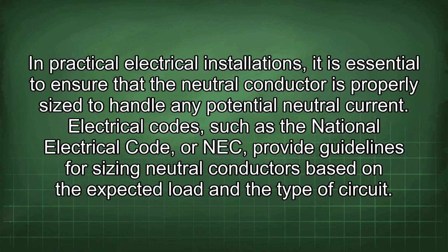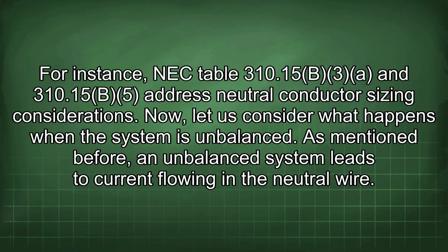In practical electrical installations, it is essential to ensure that the neutral conductor is properly sized to handle any potential neutral current. Electrical codes such as the National Electrical Code, or NEC, provide guidelines for sizing neutral conductors based on the expected load and the type of circuit. For instance, NEC Table 310.15(B)(3) and 310.15(B)(5) address neutral conductor sizing considerations.